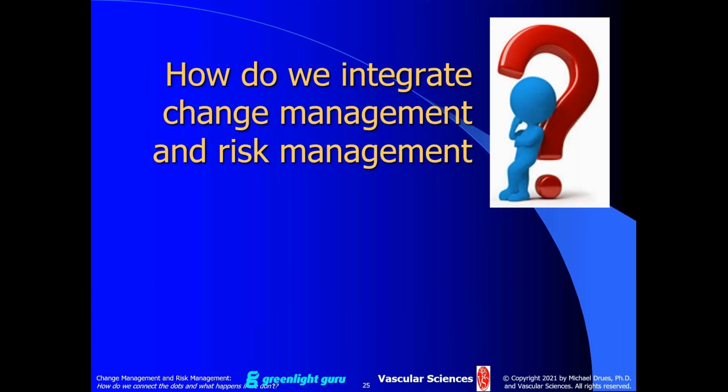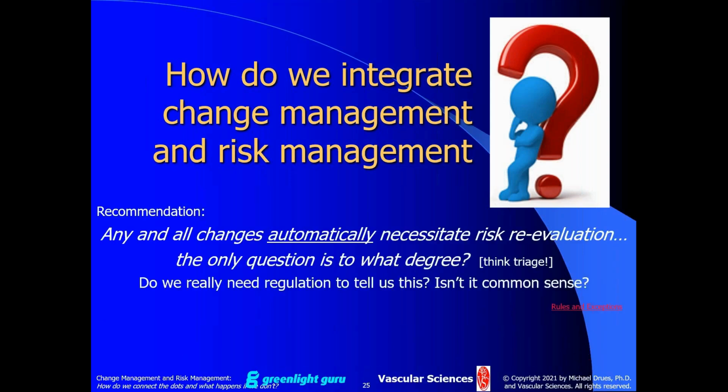So let's go further. How do we integrate change management and risk management? My simple recommendation, and this is Mike Drew's recommendation, not just as a regulatory consultant, but more importantly, as a professional biomedical engineer. It's very simple. Any and all changes, I don't care what they are, and again, we'll look at some examples in a moment, should automatically necessitate a risk reevaluation. Any and all changes should automatically necessitate a risk reevaluation.